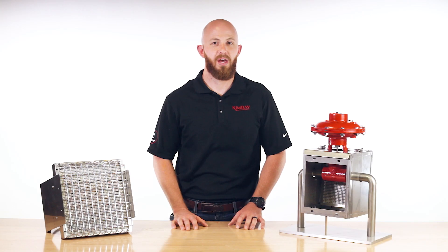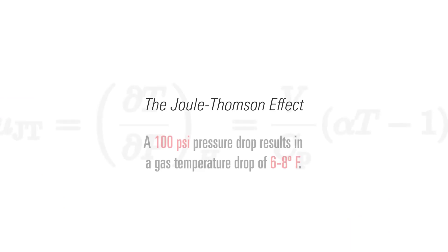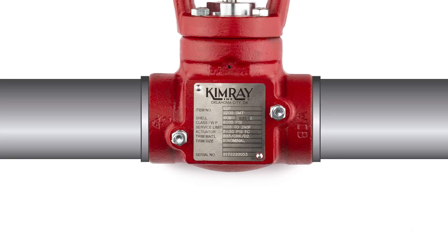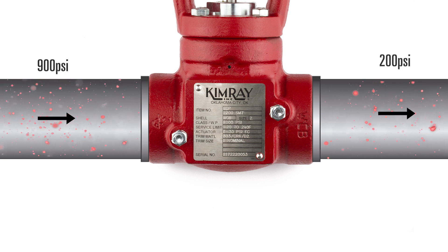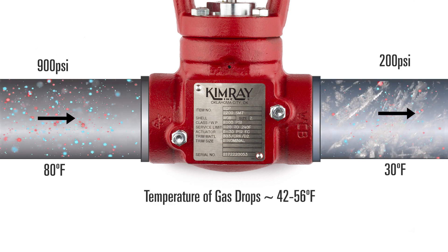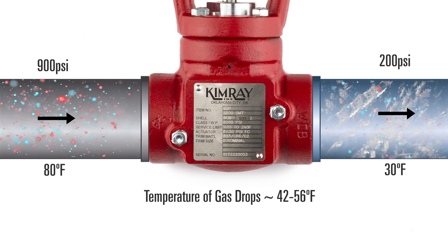The primary reason valves freeze is due to pressure drops in the gas flowing through them. The Joule-Thomson effect states that for every 100 psi cut across a valve, the gas experiences a temperature drop of six to eight degrees Fahrenheit. All gas carries some element of moisture in it. This means that when your operation includes significant pressure drops, you need to be aware of the potential for freezing. This is even more likely when ambient temperatures drop below 32 degrees Fahrenheit.